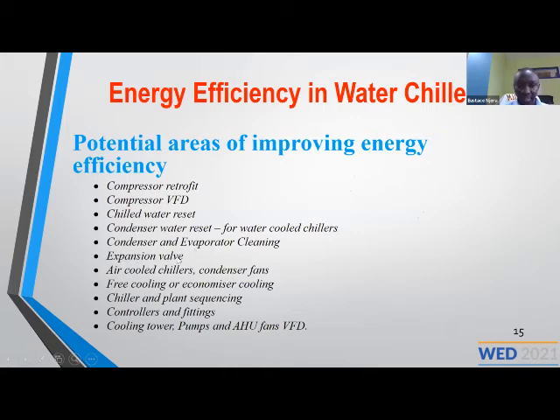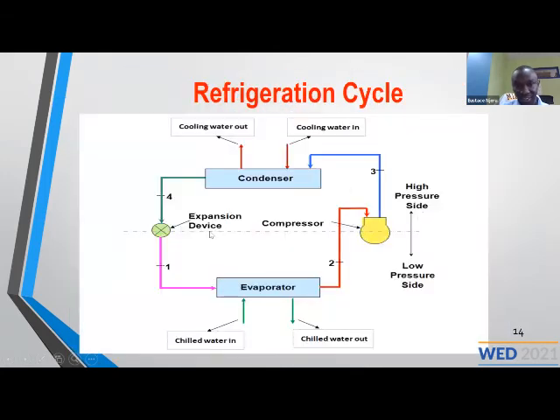Currently, the thermal expansion valves are the old ones, and they use a fluid to detect the changes in temperature of the refrigerant, so that they can control the amount of refrigerant which is flowing in the refrigeration cycle. In this refrigeration cycle, immediately after the condenser, the refrigerant becomes a liquid. Immediately after that, we have a reservoir to hold some of the refrigerant. And that refrigerant is released to the evaporator depending on the cooling load which is in the evaporator.